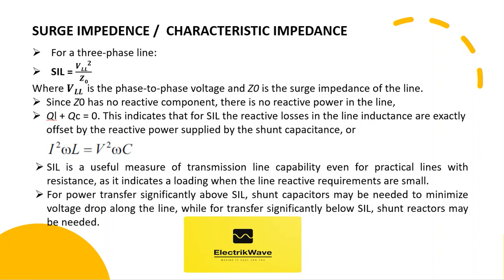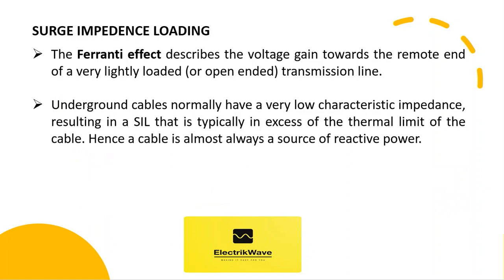For power transfer significantly above SIL, shunt capacitors may be needed to minimize voltage drop along the line, while for transfer significantly below SIL, shunt reactors may be needed. The Ferranti effect describes the voltage gain towards the remote end of a very lightly loaded, or open-ended, transmission line. Underground cables normally have a very low surge impedance, resulting in a SIL that is typically in excess of the thermal limit of the cable. Hence a cable is almost always a source of reactive power.